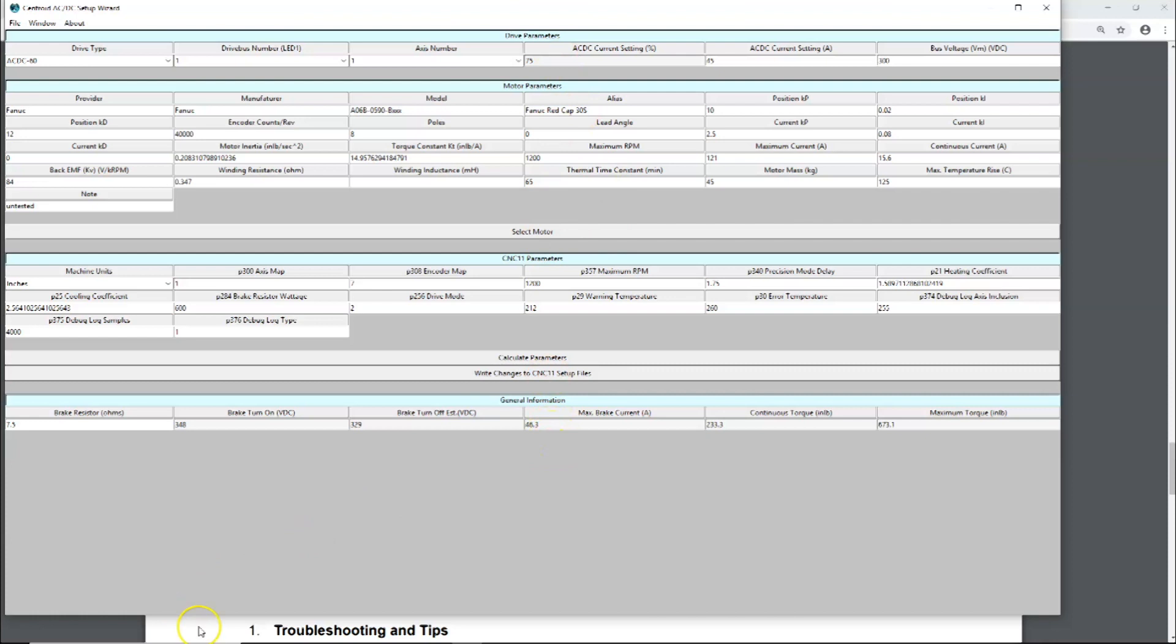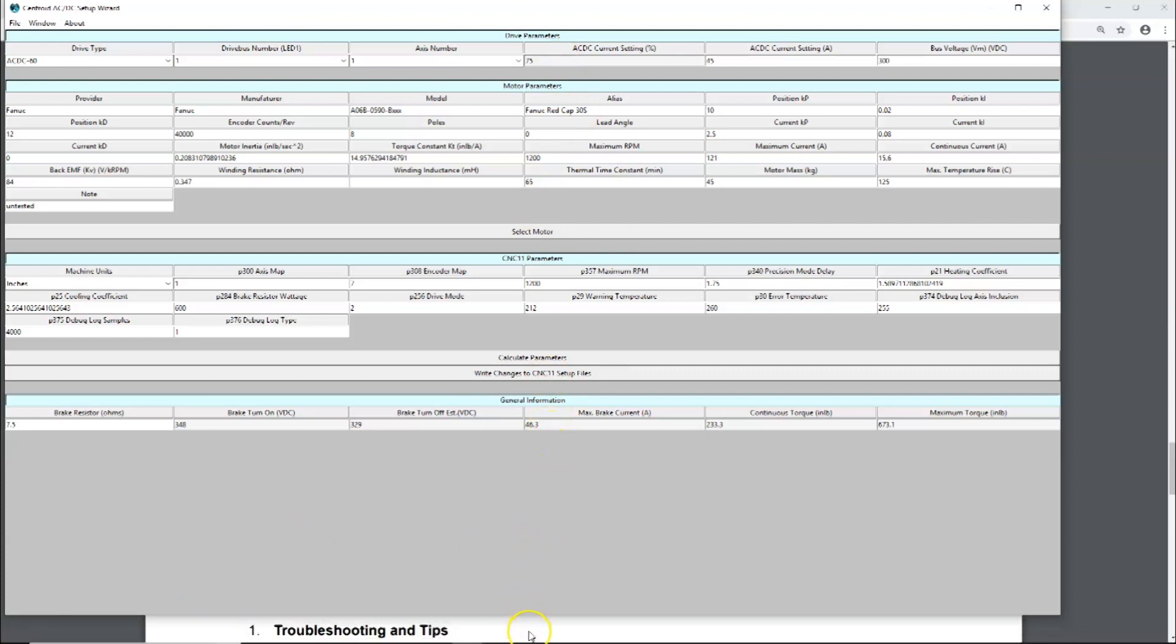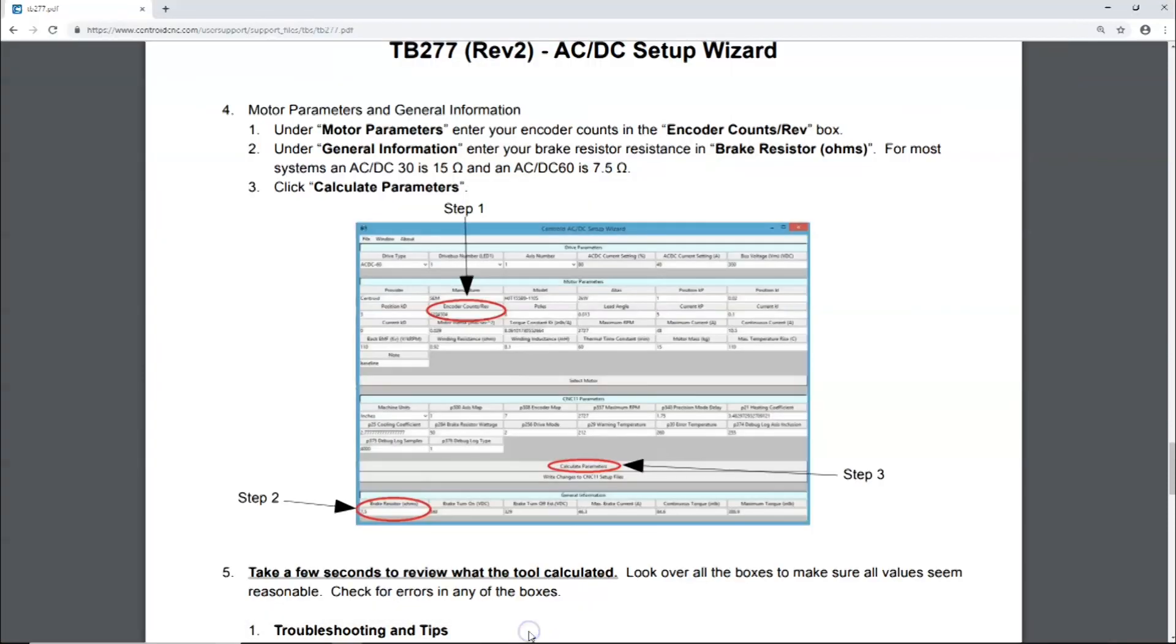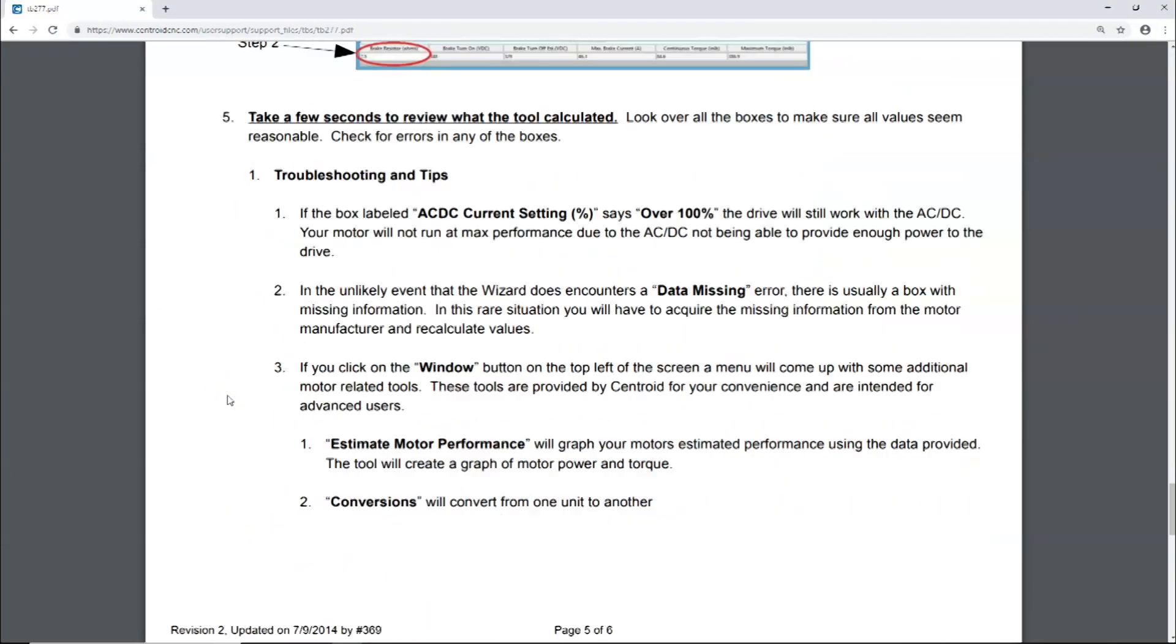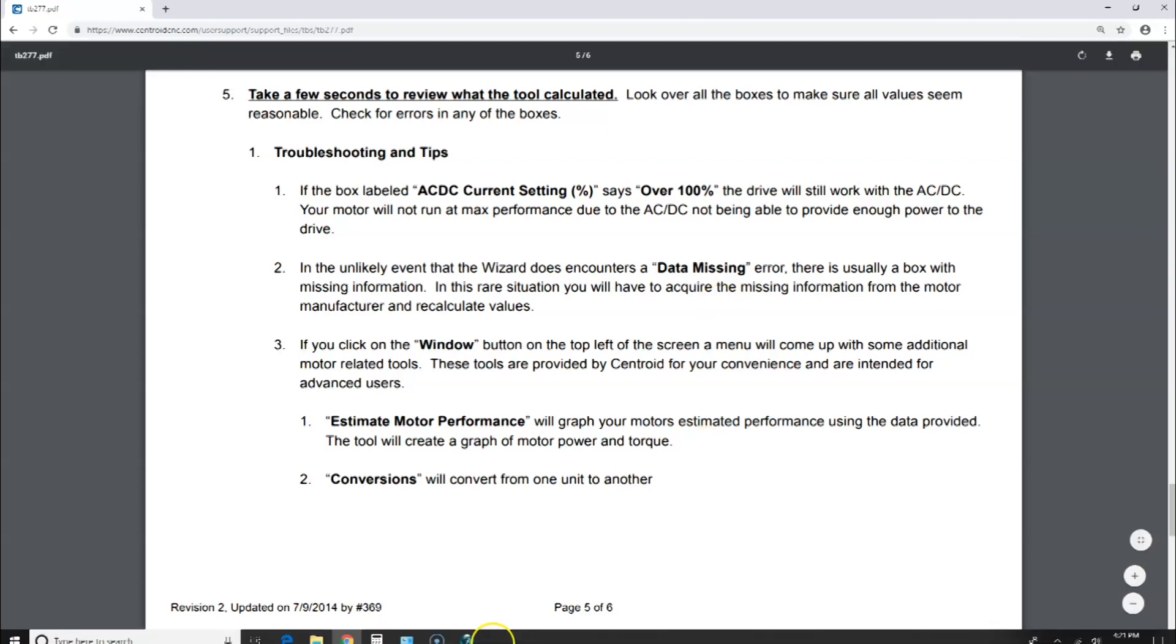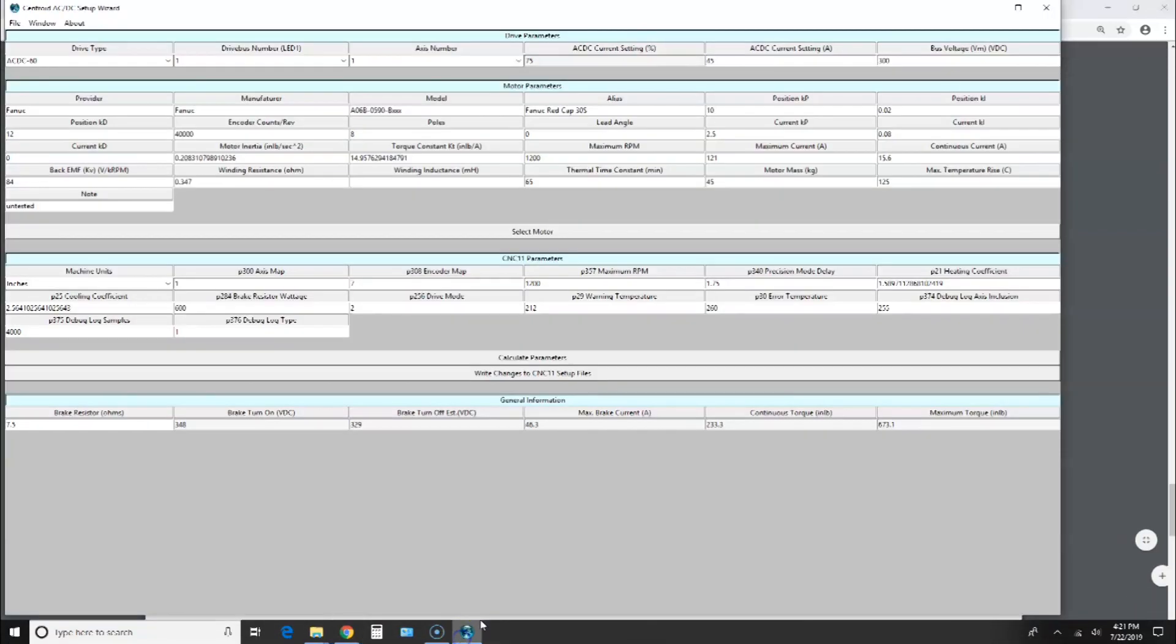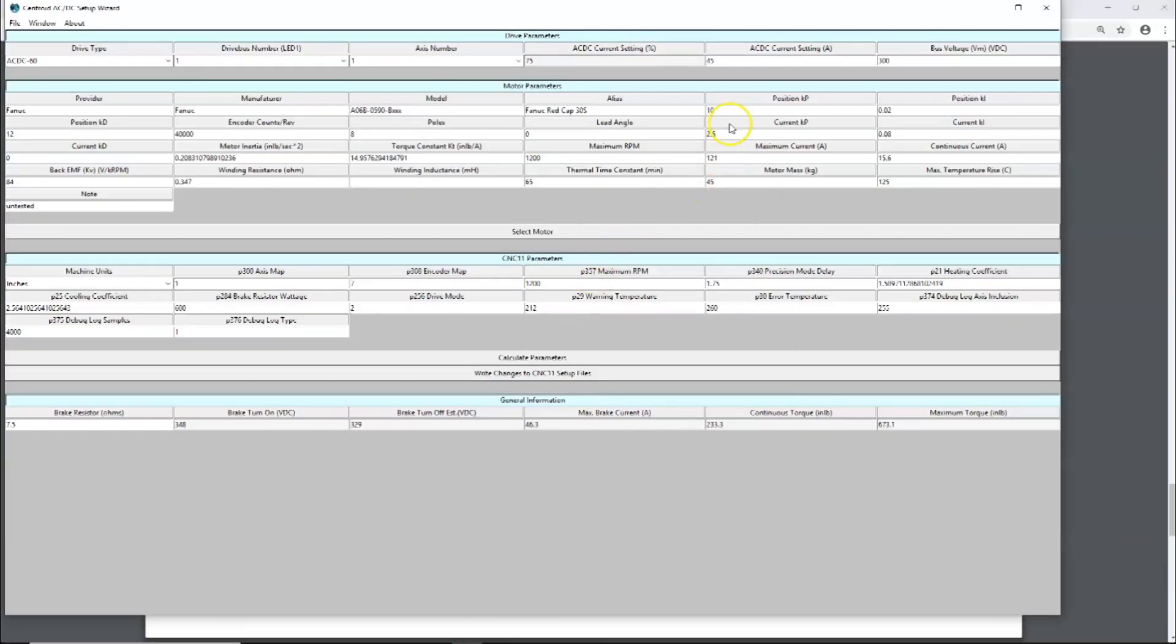Let's go down here to the troubleshooting tips in case you need them. If the box labeled AC/DC current setting percent says over 100%, the drive will still work with AC/DC, but your motor will not run at max performance due to AC/DC not being able to provide enough power to the drive. In our case, it had no problem. We've got 75% right here.